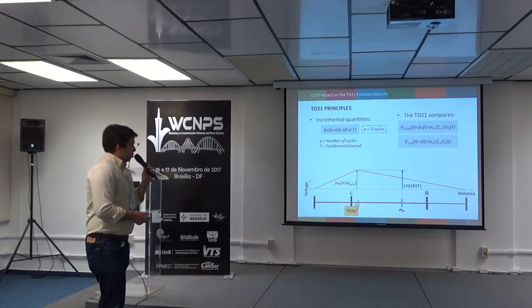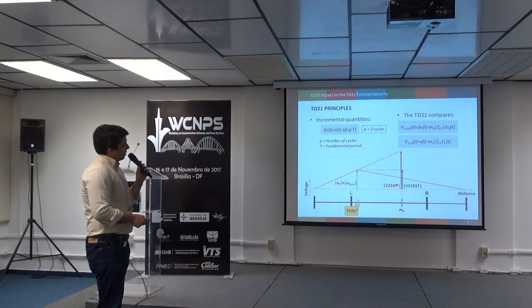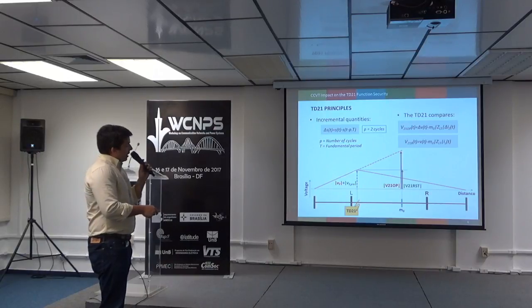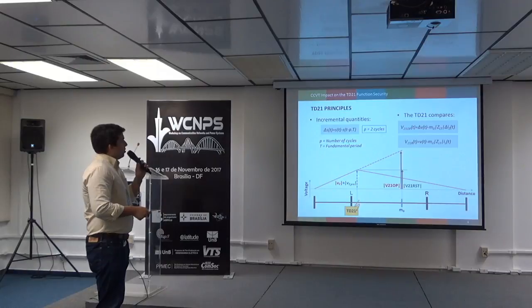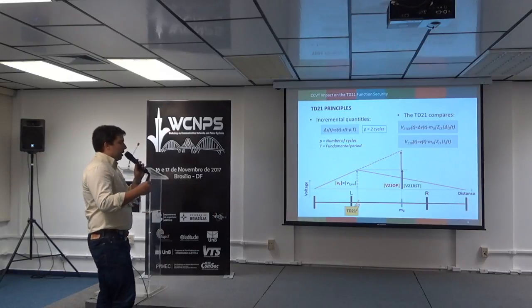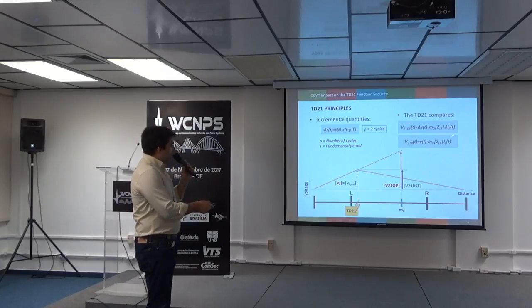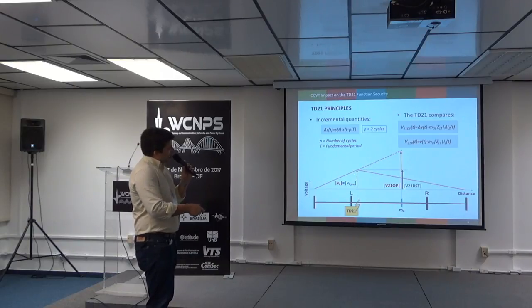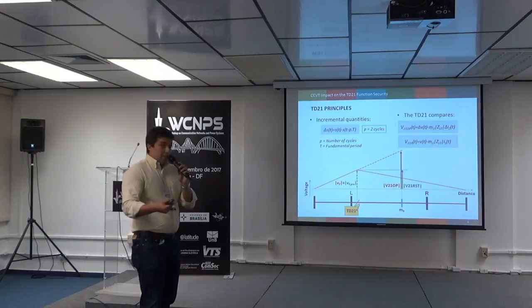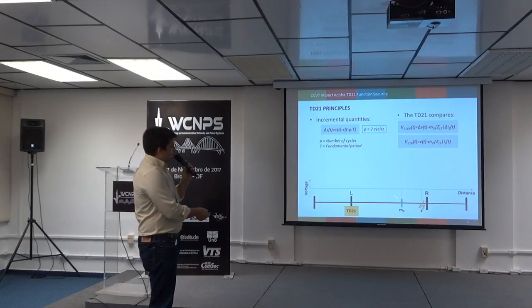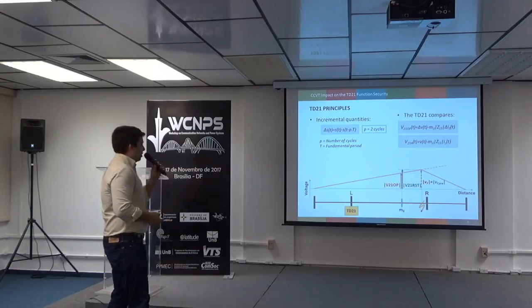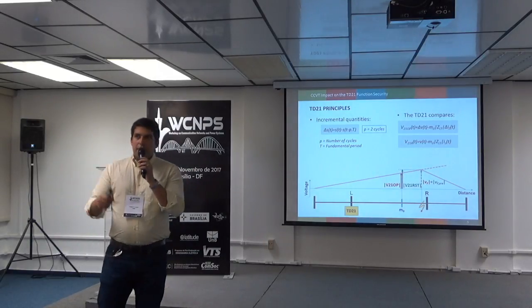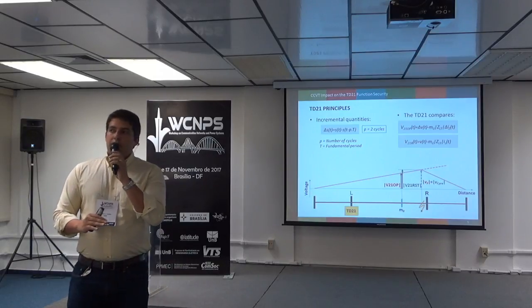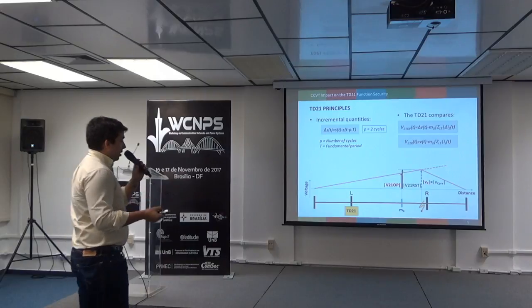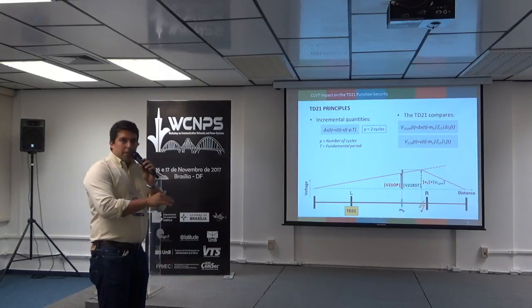Since we are using only one terminal measurement, we can estimate this voltage, but we are not able to estimate what is happening beyond the fault. We have a linear equation, so the operating voltage tends to be greater than the restraining voltage for internal faults, within the protected zone. But when the fault is outside the protected zone, and we apply the same methodology, we would obtain an operating voltage smaller than this restraining voltage. So we can distinguish internal from external faults with respect to this protected zone.